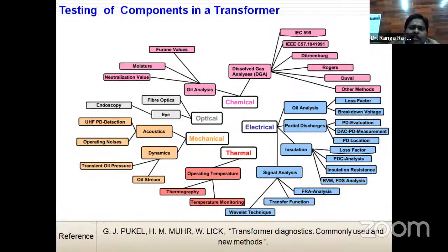There are many tests available in the field through which we can determine the current status of the insulation. Generally in the field they conduct tests very rarely, once in a year, once in 2 or 3 years, and in some stations they don't test even for 20 years. Then one day they find that the transformer is burnt.